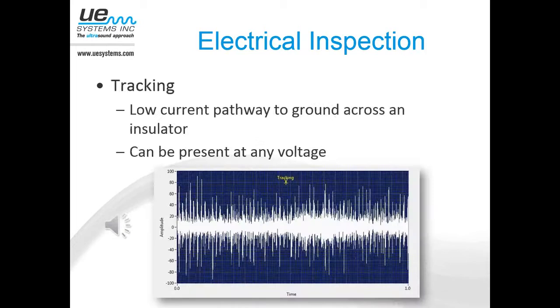We've also got the next level, where corona left unchecked becomes what's called tracking, which actually creates a low current pathway to ground. It's not actually failed yet, it's not arcing, but the failure can occur at any time. One of the telltale signs that you've got a tracking condition is a tremendous amount of amplitude change. It gets louder and softer, and you can actually hear what we call mini arcing, popping and cracking inside of there. So I'm going to play this sound file.